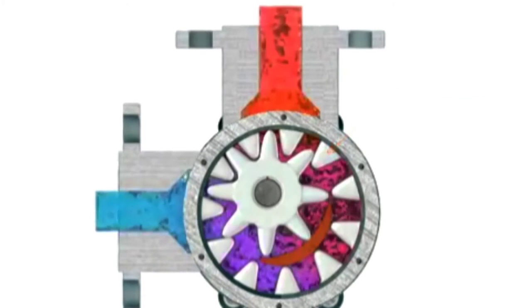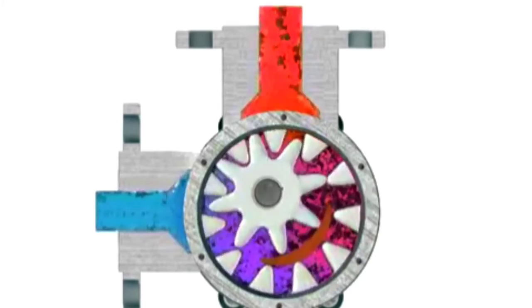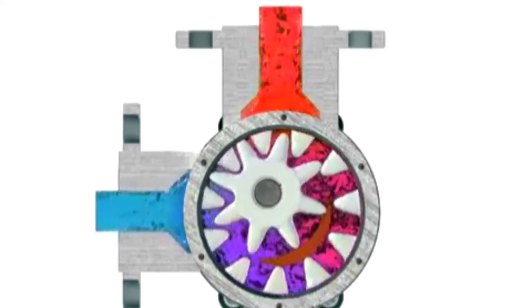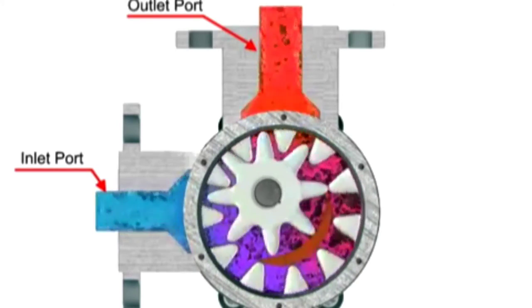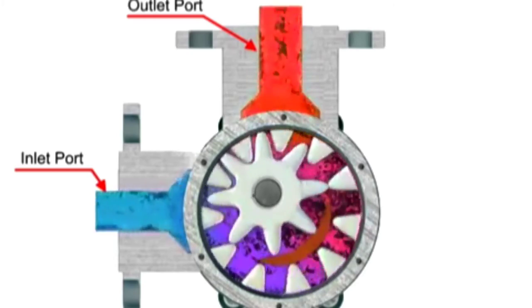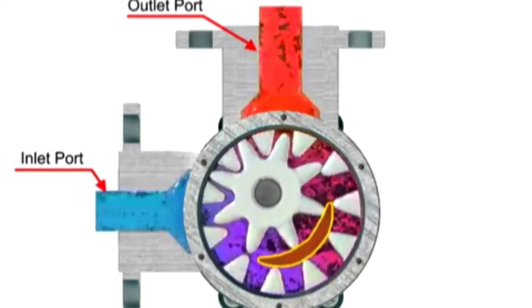As the inner gear rotates, it meshes with and moves the outer gear. Liquid is trapped in the gear spaces and carried from the inlet to the discharge. A stationary crescent shaped divider separates the intake and discharge portions of the fluid.